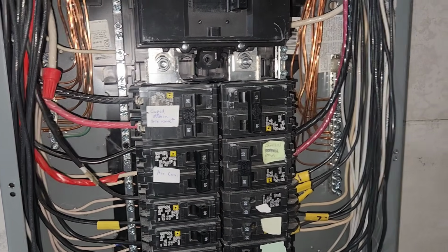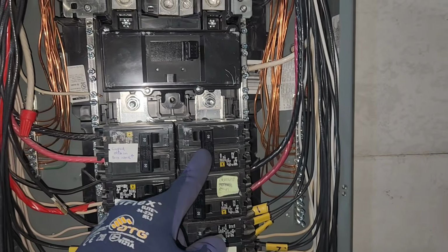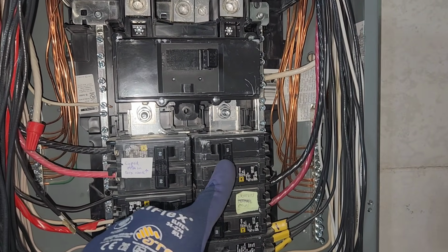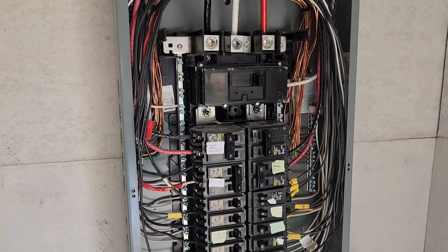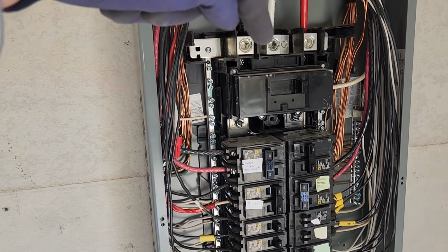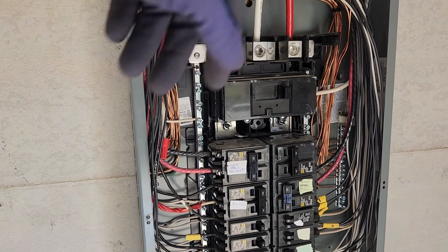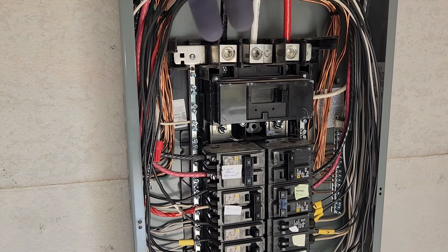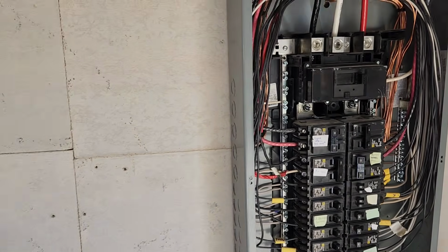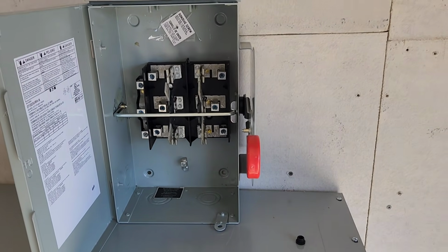With a backfed breaker, you're also limited to the amount of power you can feed through the breaker you're putting in place. So a better option is to just always feed power through the top of your electrical panel, or the main feeds of your electrical panel, whether they're on the top or the bottom. And that is where this guy comes into place.